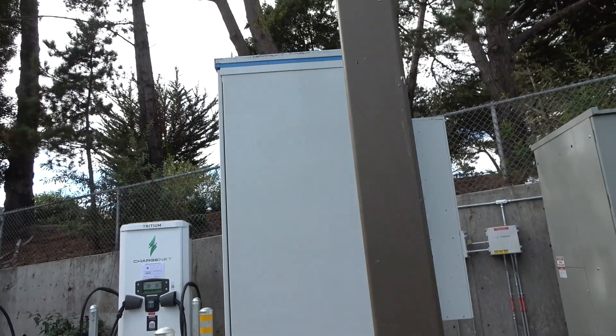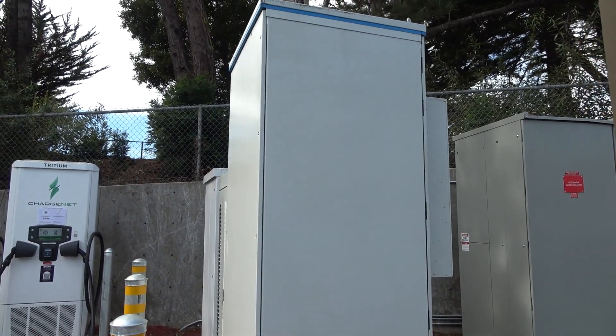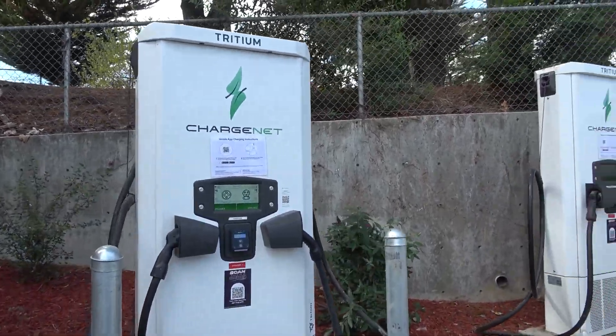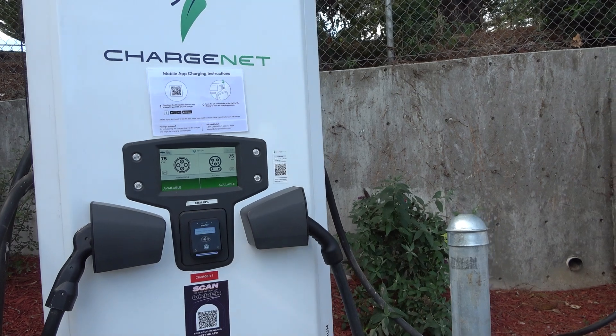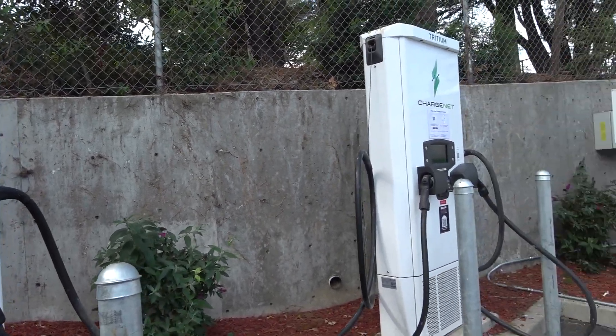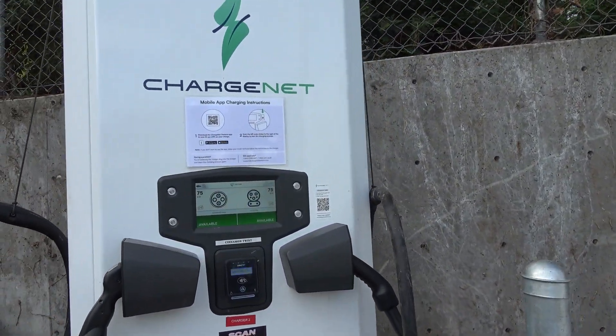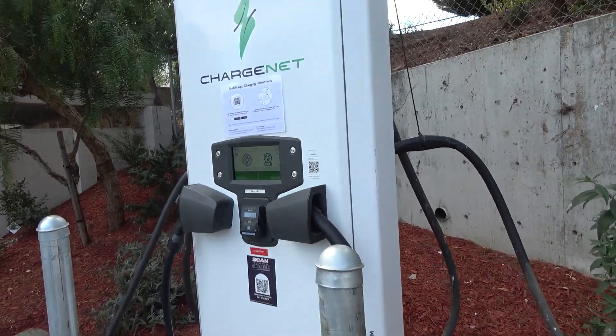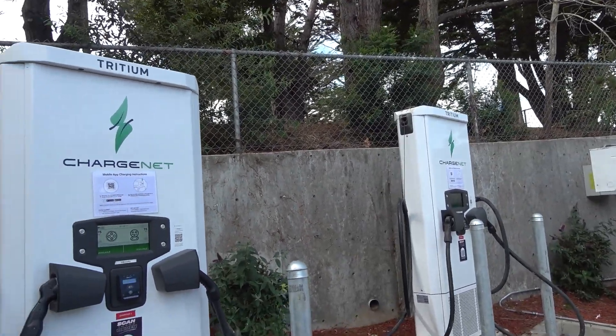Realistically, you can't have these high-power charging sites everywhere unless you're also going to be offsetting that huge demand they're going to put on the grid. This site, with six 75 kilowatt chargers, is really only adding about 450 kilowatts draw at peak — and realistically you're probably not even going to see that, maybe around 400 kilowatts would be the most ever drawn from this site. With the solar array and the battery, you could offset a good portion of that and really bring down those demand charges for sporadic, interim usage.